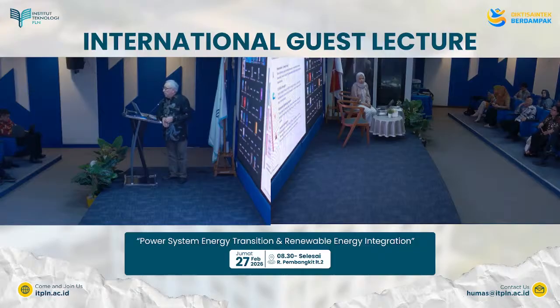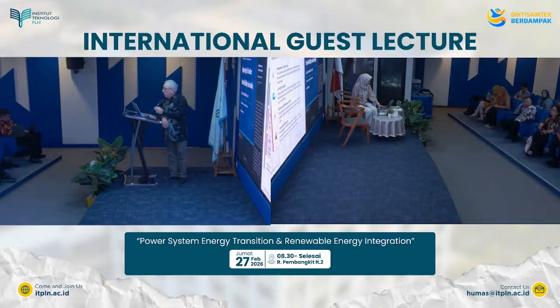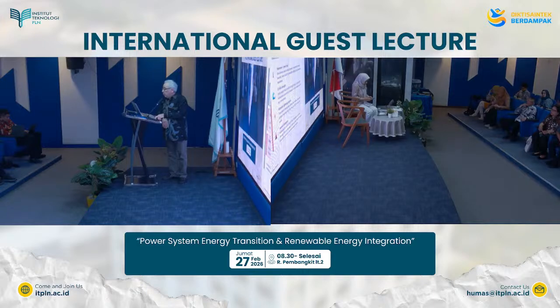And then the second important stress scenario is El Nino drought, and hydro output falls between 30 to 40% in drought years. Sumatra and Kalimantan systems are the most exposed systems. Coal or diesel must fill this gap immediately so that the system keeps operating. Monsoon, lightning storms, transmission fault spike during storm seasons, basically because of the lightning strikes. High inverter-based resource systems have less fault ride-through because of their short circuit ratios. Rate of change of frequency relays trip earlier in such instances. And when they trip early, that means it can lead to cascading failures.